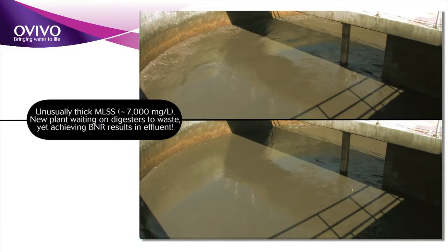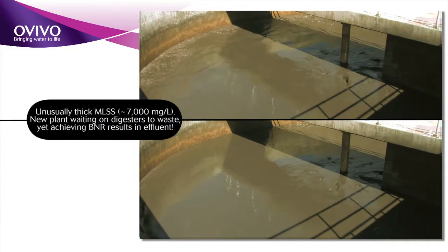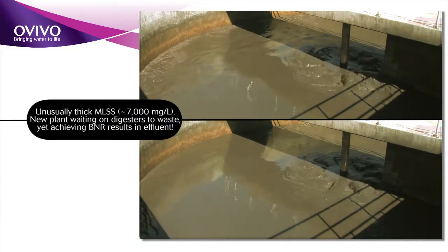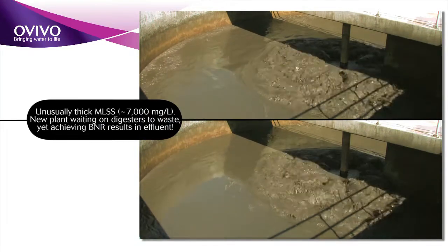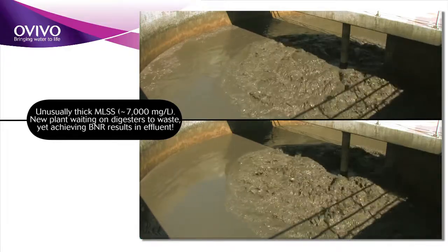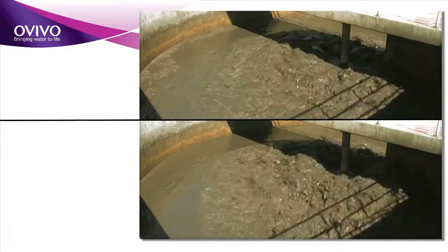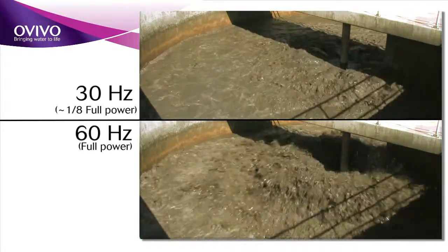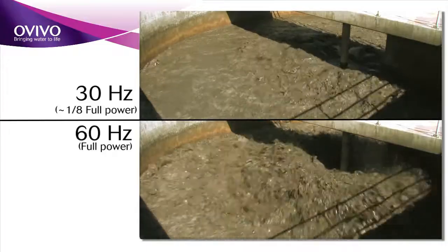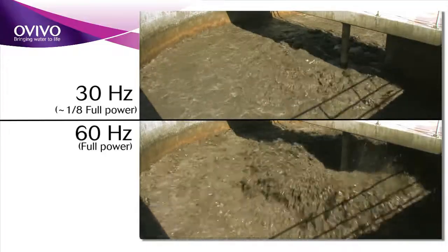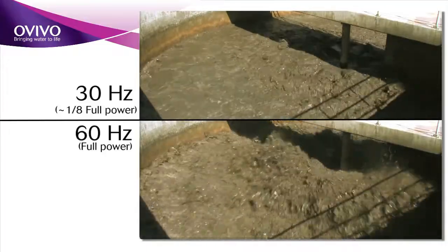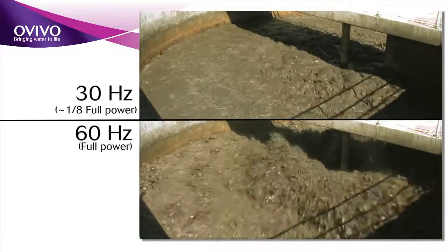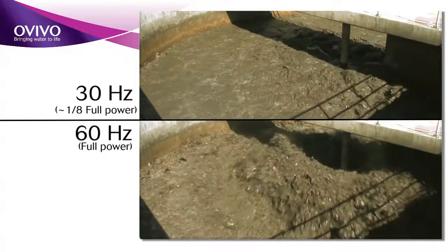Using a variable speed drive, an accelerator with the lower impeller can reach turndown levels of 80 to 90 percent. This can result in significant energy savings, considering that a 100 horsepower aerator can be slowed to operate at only 10 horsepower during periods of low loading while still completely mixing the basin.